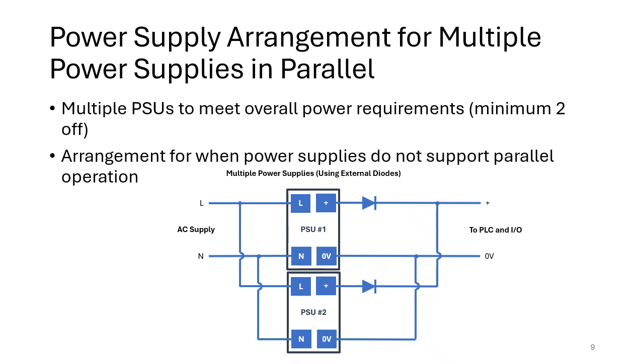So one thing we can do with these redundancy modules is we can use MOSFETs instead of diodes, and a MOSFET, it's still an electronic device, but it has a much smaller volt drop. That can also affect the heat dissipation as well, because where there's a volt drop, you're dissipating power, which causes heat. So it can be useful to have a MOSFET which has a lower volt drop, and that implies less heat generation as well. So that can make your panel arrangement simpler, and it means you're wasting less power.